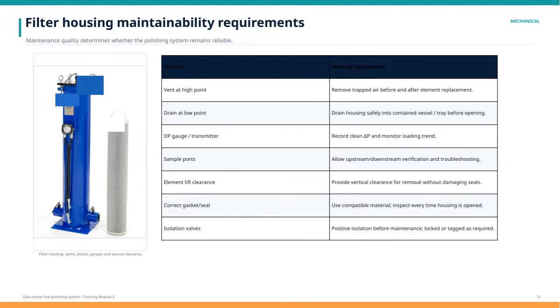Maintaining the filter housing is crucial to ensuring that our fuel polishing system remains reliable over time. The quality of maintenance directly impacts system performance, so it's important to focus on several mechanical features that must be properly handled. First, vents located at the high point of the housing are used to remove trapped air before and after replacing filter elements, preventing airlocks that could compromise operation. Drains at the low point allow safe removal of fluids by directing them into a contained vessel or tray before opening the housing, minimizing spills and hazards.